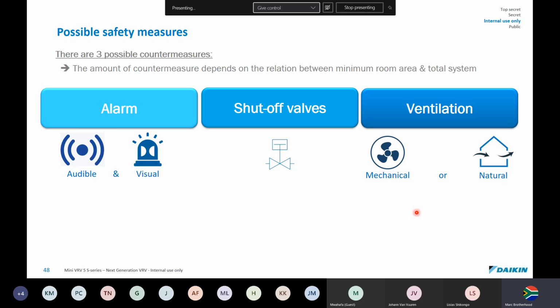So there are three possible countermeasures that you can have in a minimum room area or in a total system. You can have an alarm system that goes off, warning you that there's a leak. You can have shut-off valves, or if there's a leak, you can ventilate. So fans can switch on, or you have automatically louvered windows that open and bring in fresh air to dilute the R32 refrigerant leak.